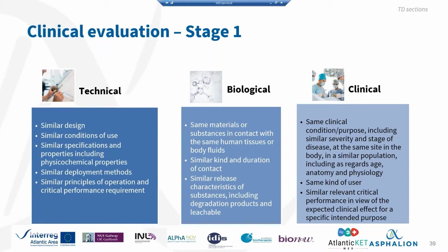that has to be equivalent within the devices. Okay, it does not work as in the legal framework of the United States. It's not the same concept of equivalence. Okay, you've got to demonstrate technical, biological, and clinical equivalence. Clinical equivalence means that it's intended for the same clinical condition, including similar severity and stage of disease, at the same site in the body, same kind of user, and similar relevant critical performance in view of the expected clinical effect. Okay, so as you see, it's a lot of information that has to be equivalent.